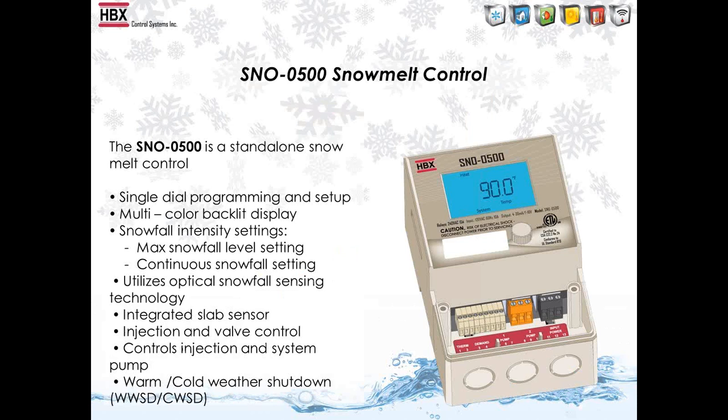The main control we use for snow melting is the Snow 500 standalone control. This will not support multiple boilers because it only has one boiler TT contact. You can do multiple mixing — either injection or valve control — and it's a single zone operation, so it works with one of our optical sensors. The control has idle, melt, and force melt demands built in. It has instantaneous and continuous snowfall settings, and you also have warm weather and cold weather shutdown.